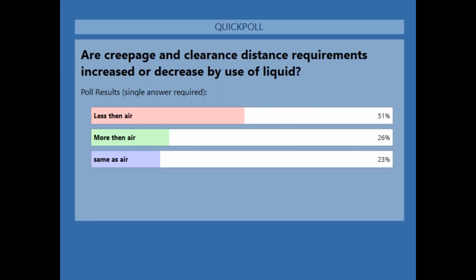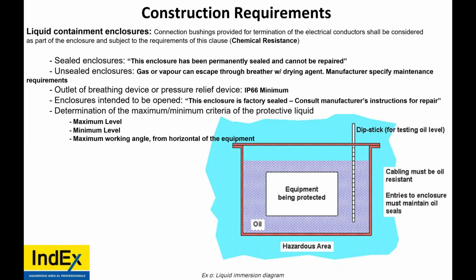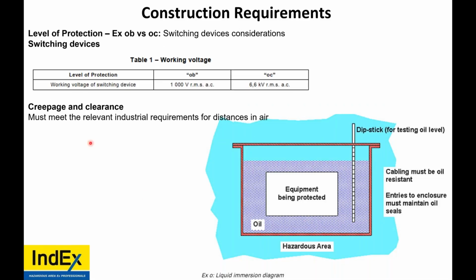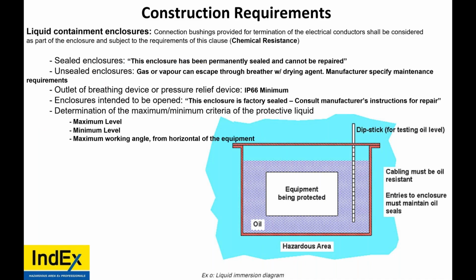So the correct answer is same as air. 23% of you got it. We go back a slide. Creepage and clearance distances must meet the relevant industrial requirements for distances in air. So the creepage and clearance distances within the oil-filled device does not change. It shall be as if it was in air.